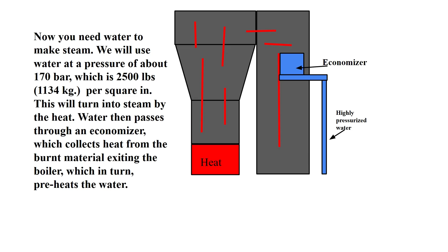preheats the water from burnt material exiting the boiler, which makes the water easier to turn into steam later on. Then the preheated water goes through a steam drum, which collects water and steam. After it sits there for a bit, it goes down multiple thousands of pipes through the boiler, which turns the water into steam. Right about at this diagonal point, the water is basically fully steam.